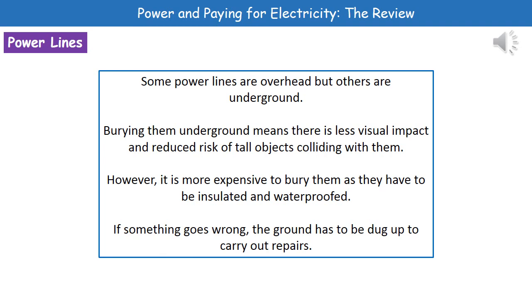However, it is actually more expensive to bury cables underground, because we have to insulate them and waterproof them — electricity and water is not a good mix. We need to ensure they're well insulated and waterproofed. The other big problem is that if there is a fault with a buried power cable, we have to dig up the ground to carry out repairs, which is more problematic, more time consuming, and obviously more costly.